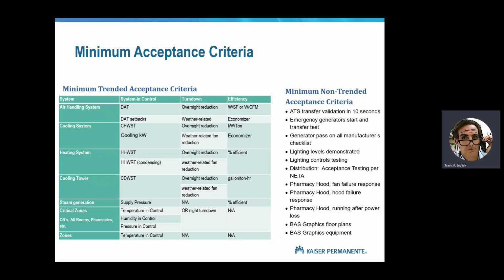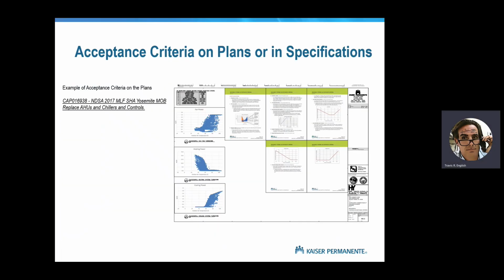And then we would look at efficiency. We look at the BTUs in the heating loop. We divide those by the BTUs in the gas train. And we want to see that number better than 80% every single day, starting at day one. And then there are some yes or no, check-the-box type of points, like failure modes. For electrical systems, we tend to have a lot of these non-trended points. And so we tell the engineer to put them on the plans. So this is an example. This is the acceptance criteria put right on the plans.